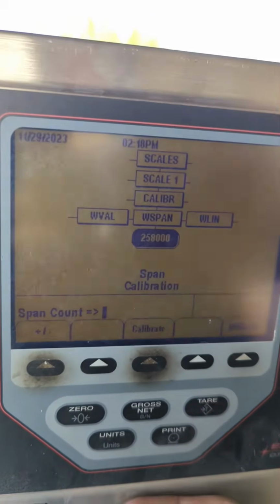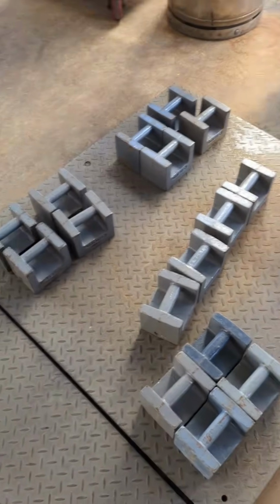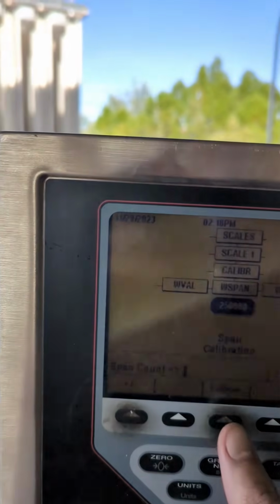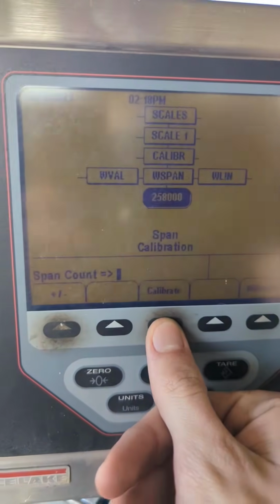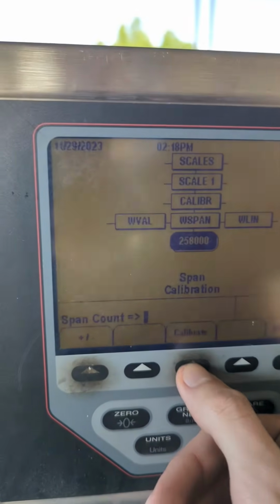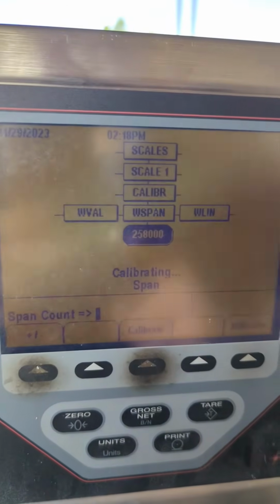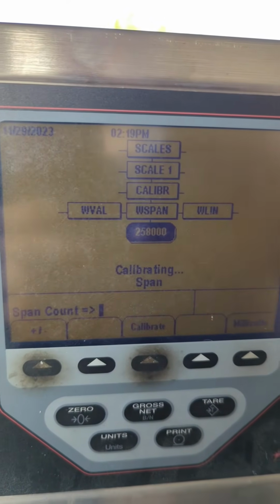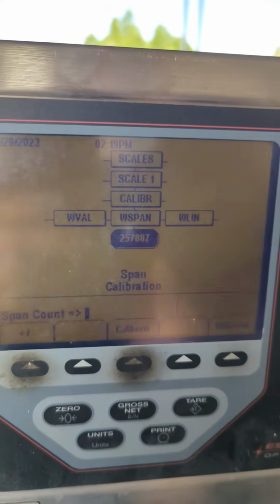All right, so we're going to focus back on that screen for a second. And now that we have the 500 pounds evenly distributed, we're going to go ahead and hit the soft calibration button again, so that arrow underneath. It's calibrating span. Perfect, it should be good now.